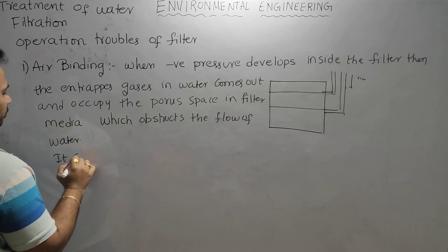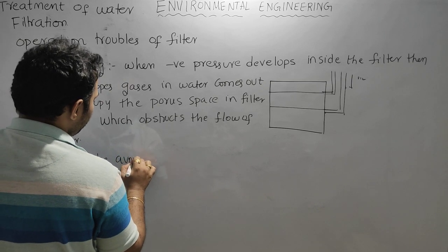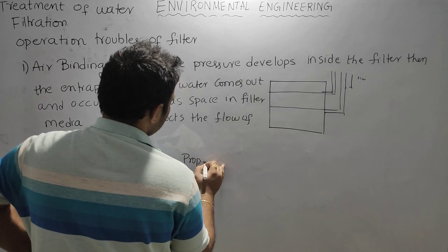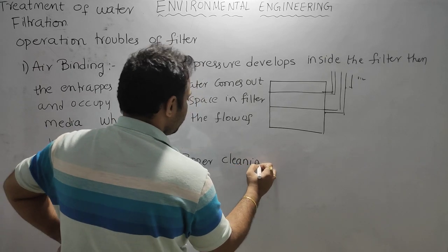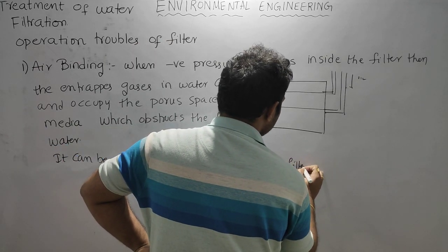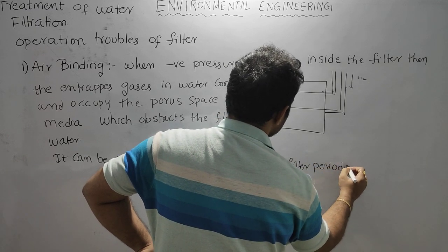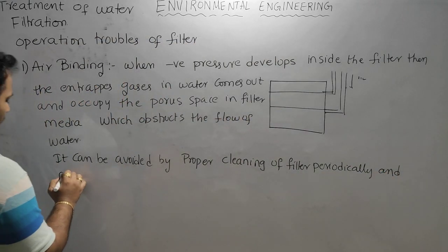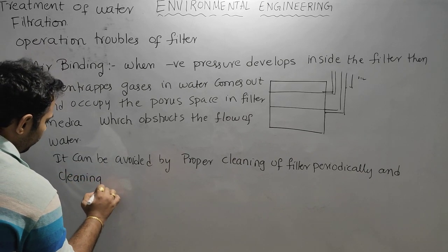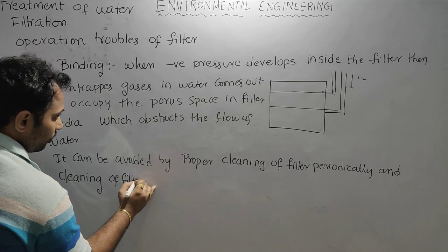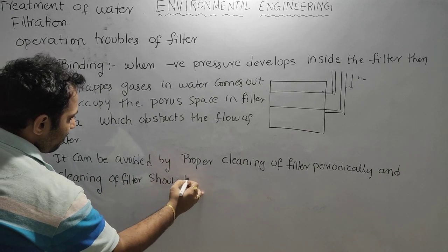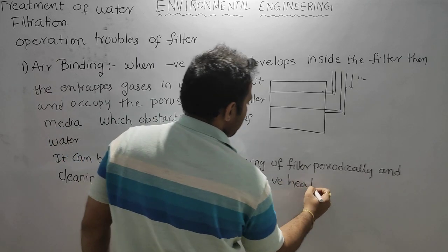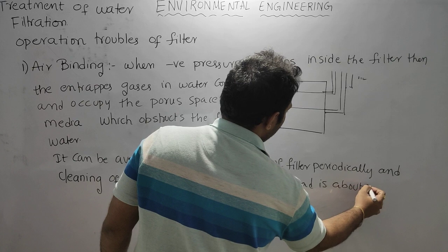So it can be avoided by proper cleaning of the filter periodically, and cleaning of the filter should be done when the negative head is about 1.2 meter.